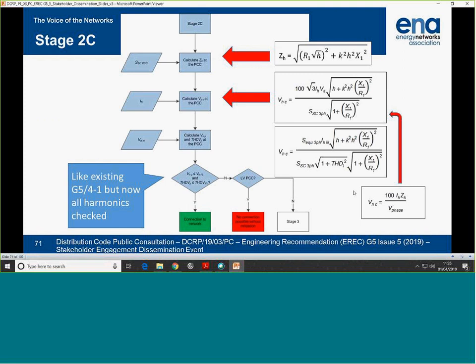Then we get to this slide. It's a bit complicated, but down the left-hand side, you've got SSC PCC, which is the short circuit fault level at the common coupling. So that's an input, and you can know how strong the network is. That's then used to derive the harmonic impedance. That equation on the right is useful because previously what we had was K times H times Z 50 Hertz, or Z1. If the X to R ratios are low, as they are with low voltage networks, the formula gives you some advantage. You're not over-egging it effectively.